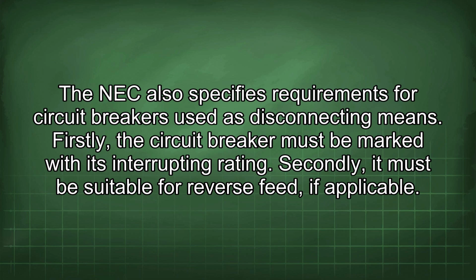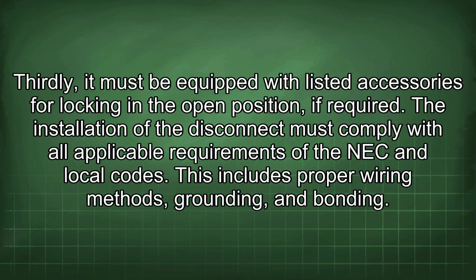Firstly, the circuit breaker must be marked with its interrupting rating. Secondly, it must be suitable for reverse feed, if applicable. Thirdly, it must be equipped with listed accessories for locking in the open position, if required. The installation of the disconnect must comply with all applicable requirements of the NEC and local codes. This includes proper wiring methods, grounding, and bonding.